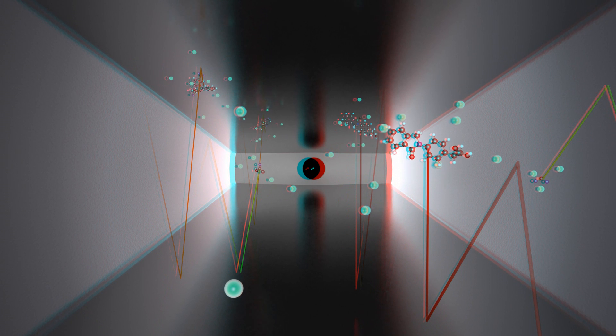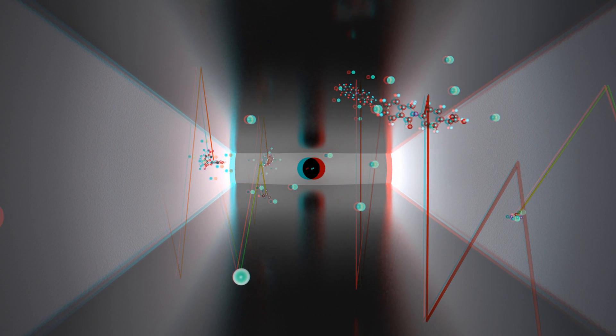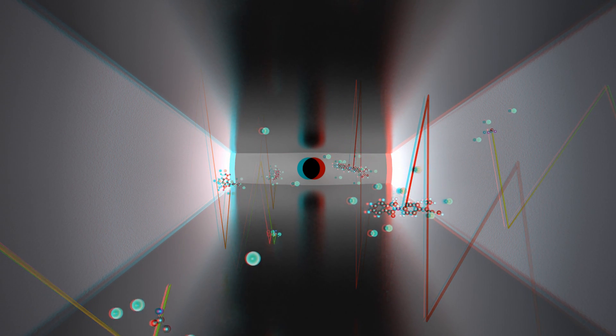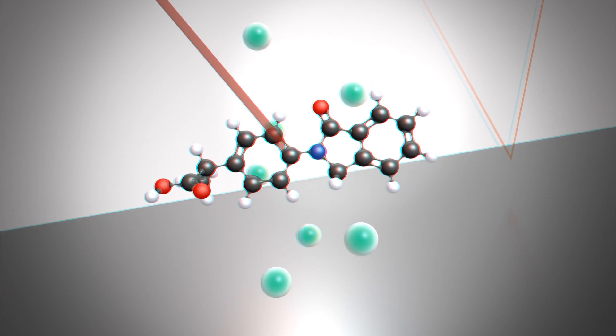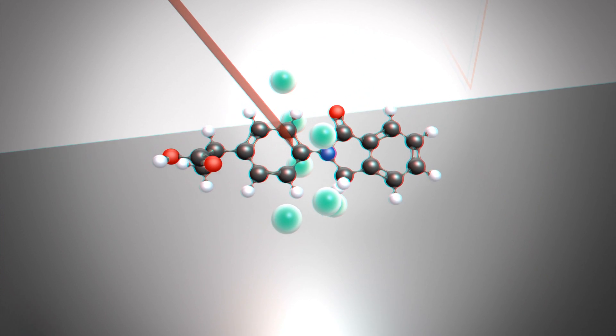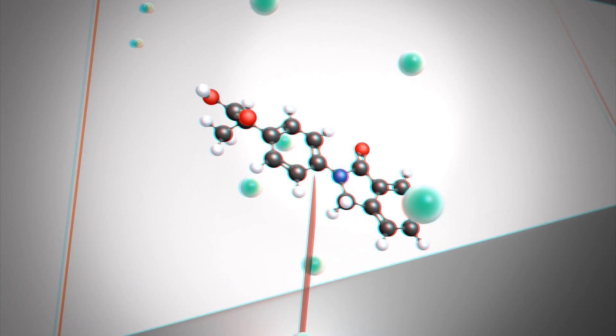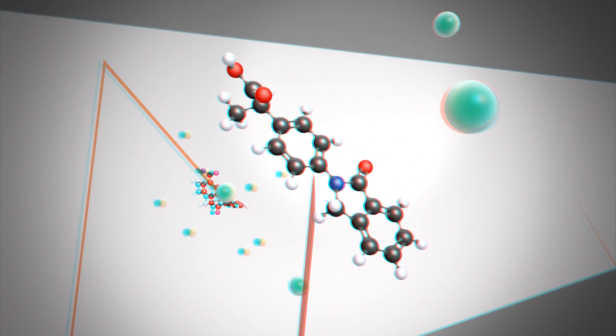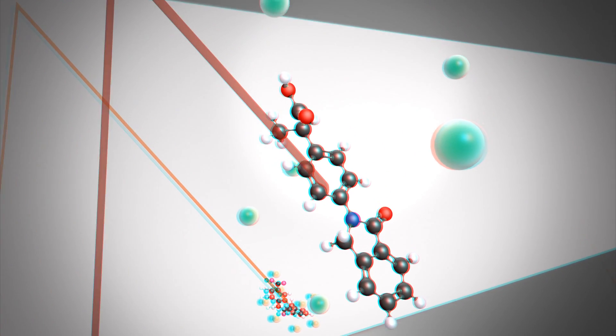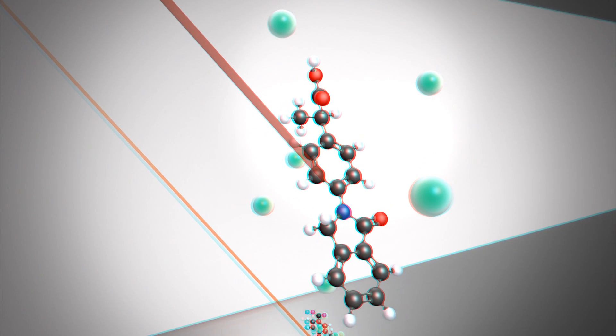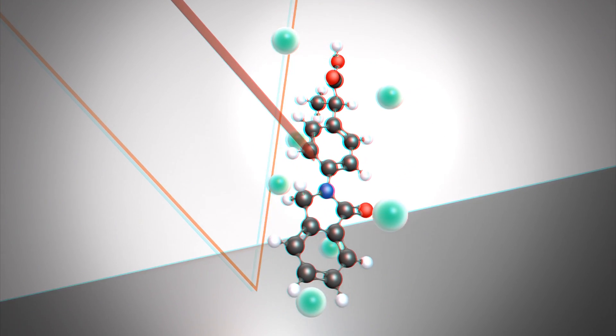Together with gas phase modifiers such as isopropanol, target ions will cluster and decluster repeatedly, resulting in enhanced differential mobilities, which enable a level of separation previously unattainable.